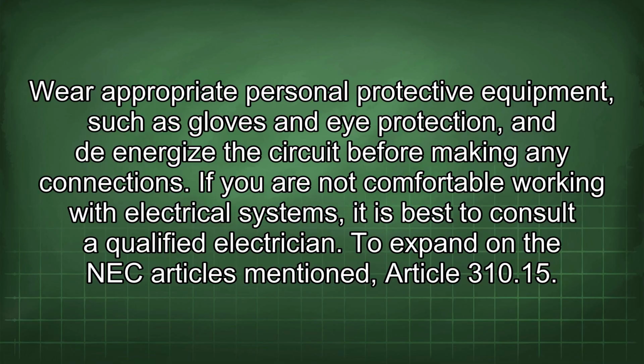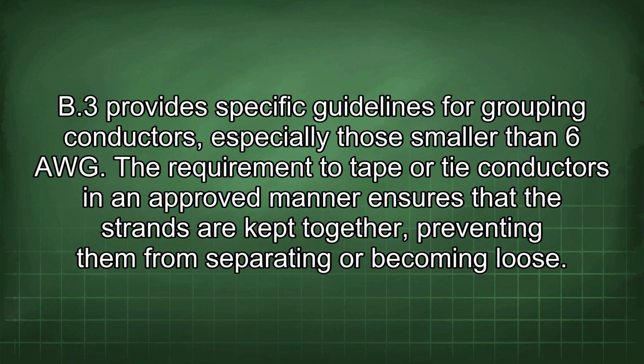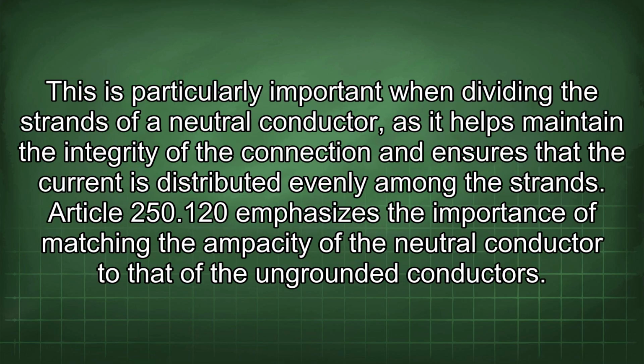To expand on the NEC articles mentioned, Article 310.15 B3 provides specific guidelines for grouping conductors, especially those smaller than 6 AWG. The requirement to tape or tie conductors in an approved manner ensures that the strands are kept together, preventing them from separating or becoming loose. This is particularly important when dividing the strands of a neutral conductor, as it helps maintain the integrity of the connection and ensures that the current is distributed evenly among the strands.